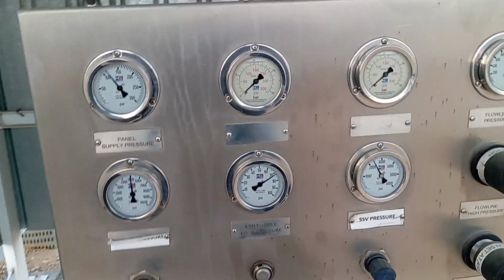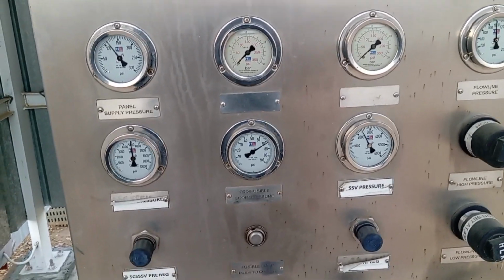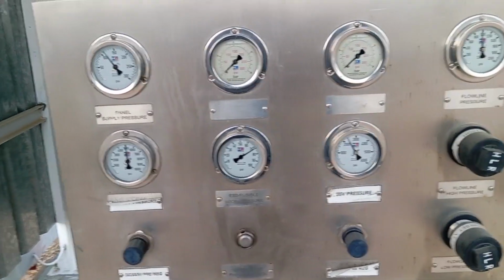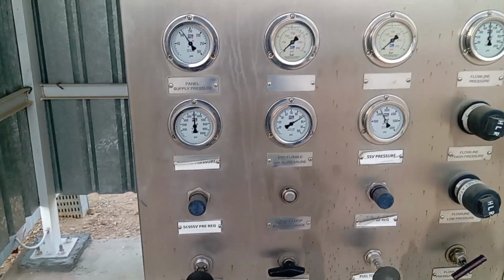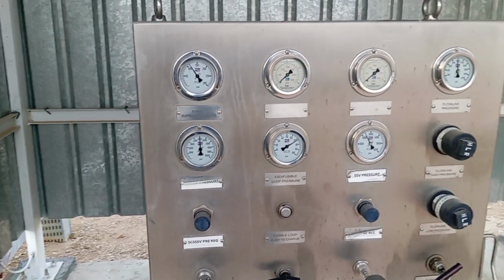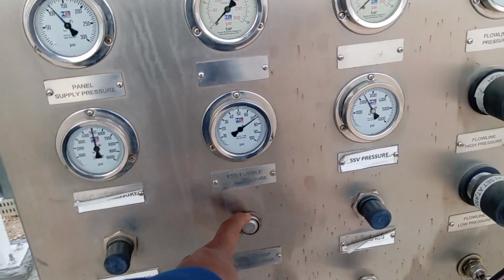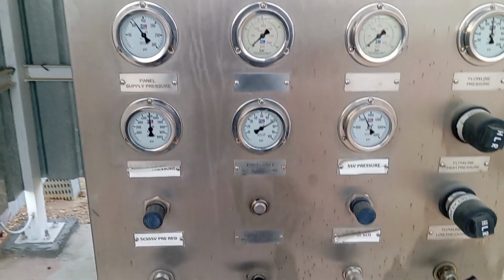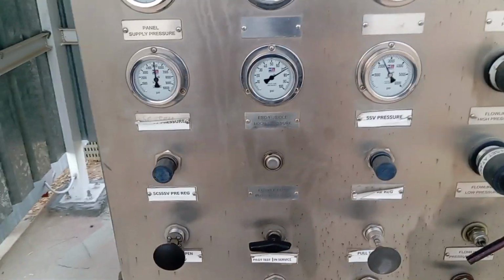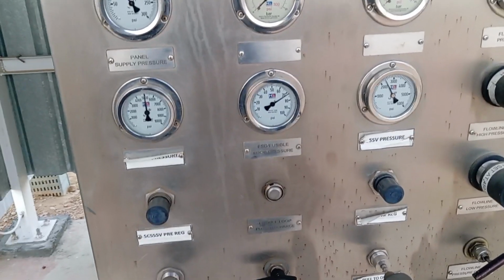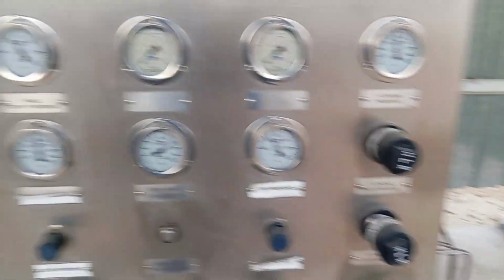And now we will discuss the starting sequence of this wellhead control panel. First of all, make sure the wellhead control panel supply is sufficient, and then make sure the pilot switches are normal and wellhead pressure is also in the normal range. And then we will charge the fusible loop through this push button. We will push and charge the fusible pressure to the normal range, 70 psi, and then we will get the command through this SOV solenoid valve from the CCR.